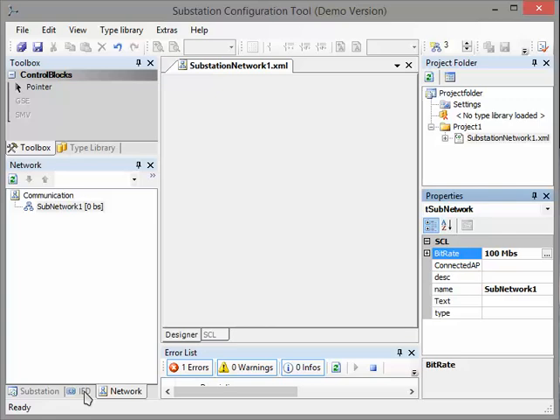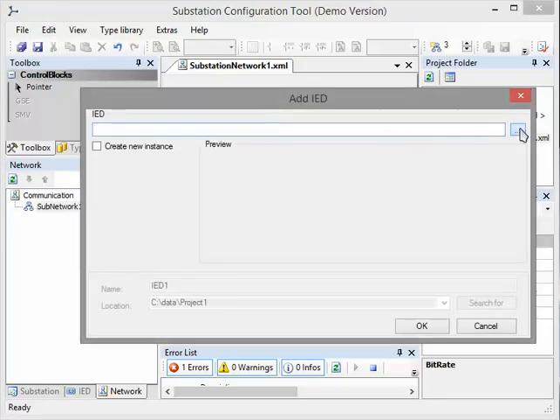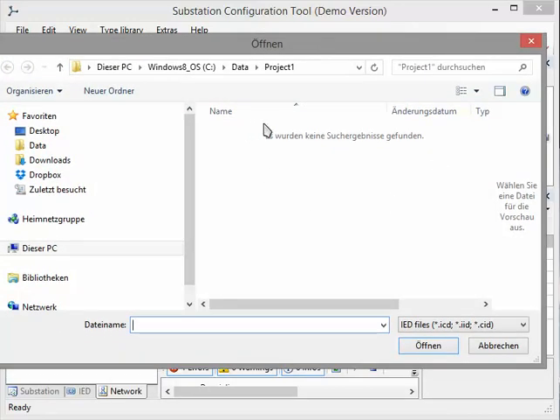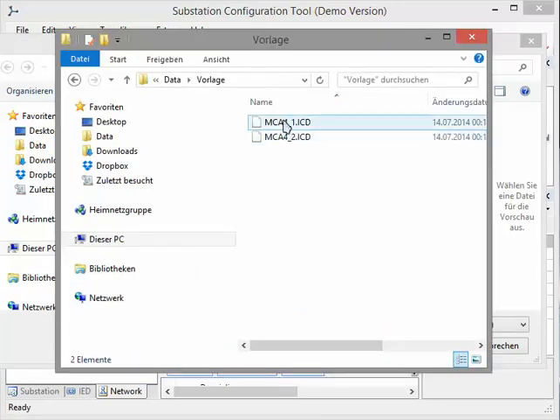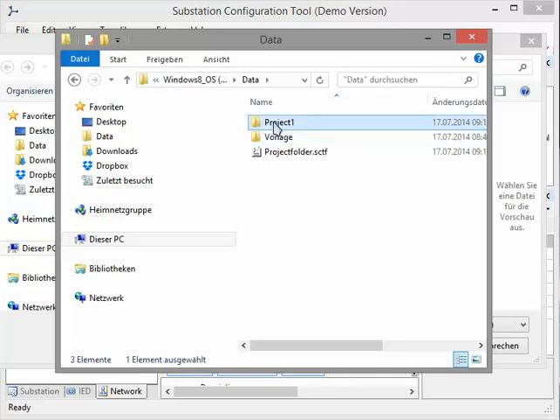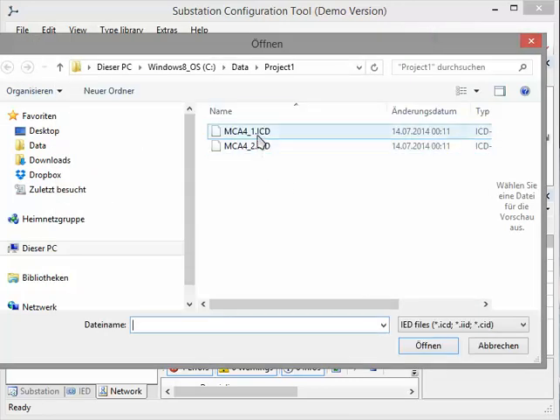The next step is that we add our ICD file from the protection relay. We do this by clicking File, Add, Available ICD. I click Open and now you see our project is empty — there are no project files. No problem. I have prepared some ICD files for us, so we will copy them from our template folder to our project folder. Now you see there are two protection device ICD files inside of our project folder and I will open the first. Let's say Open.